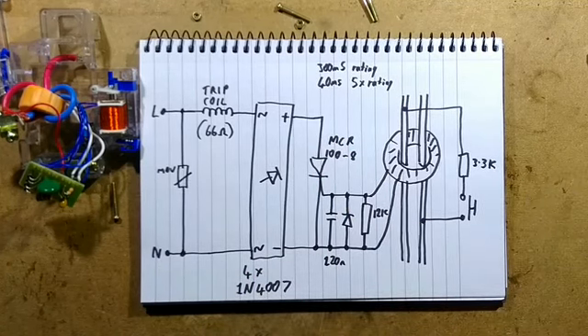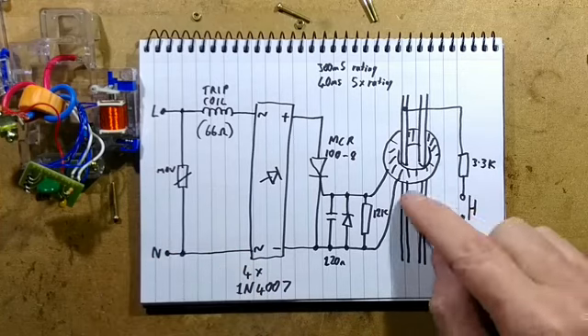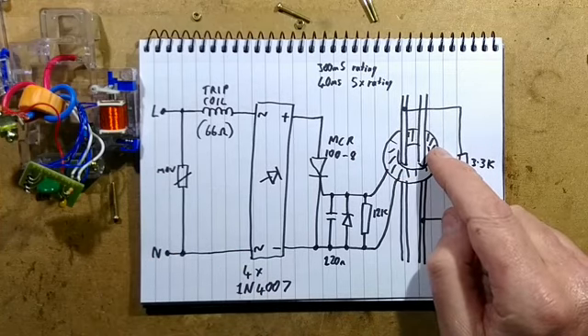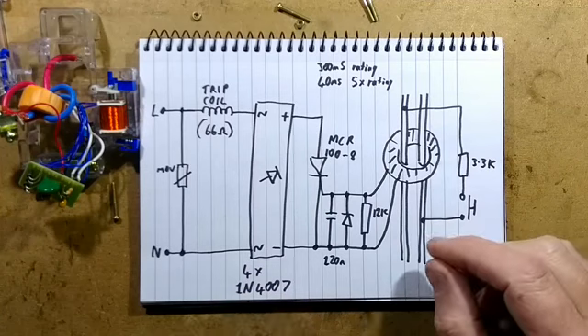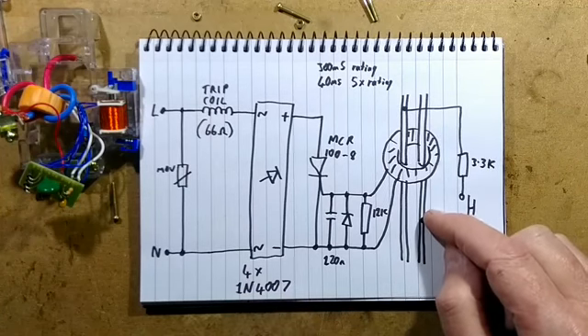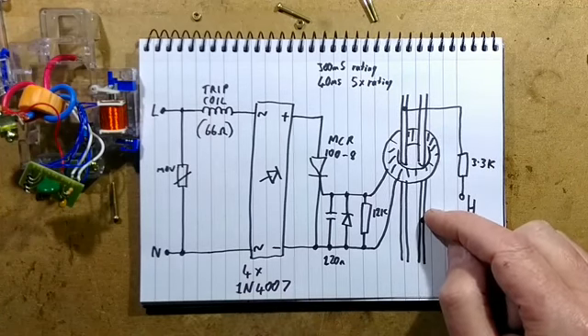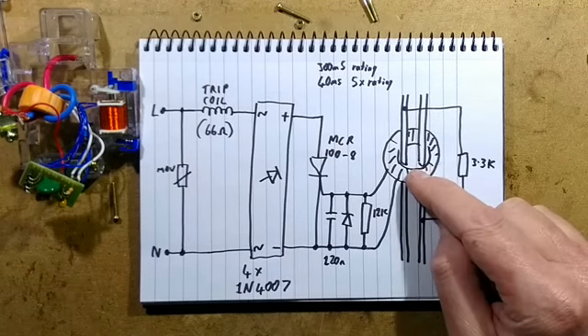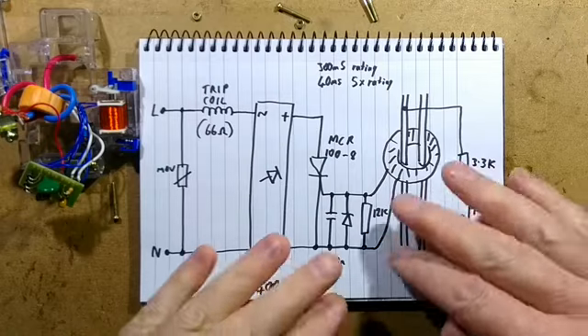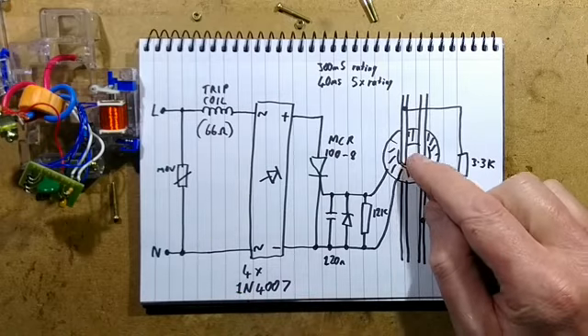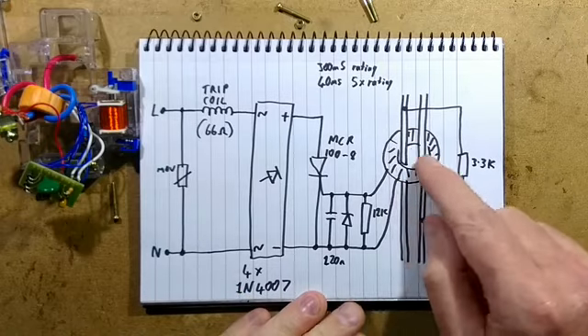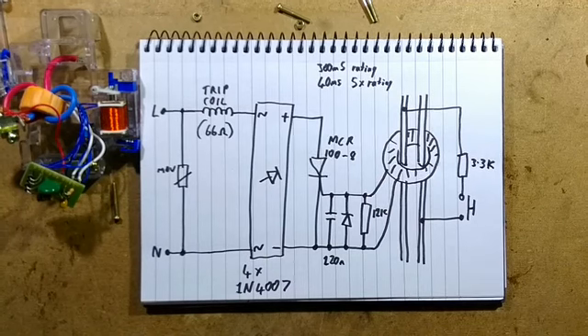This fulfilled that, even though it was effectively only going to trigger on 1/2 of the wave. I was under the impression it had to trip within half a sine wave, but really they're just saying trip within the best part of a sine wave. And this is just tripping in either less than the half, or on the other opposite polarity, it'll be just over half a sine wave, so it goes into the other polarity. That's very good.